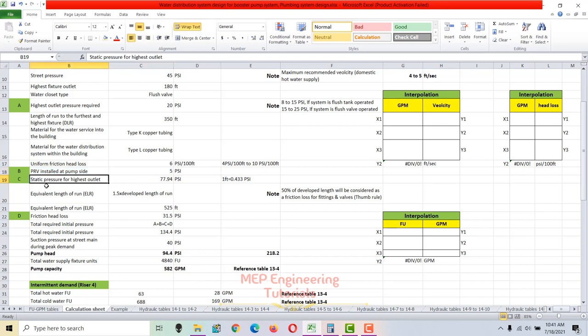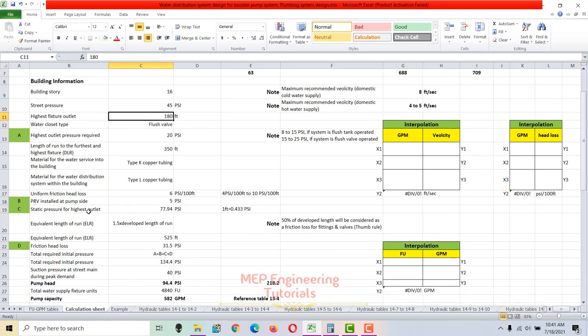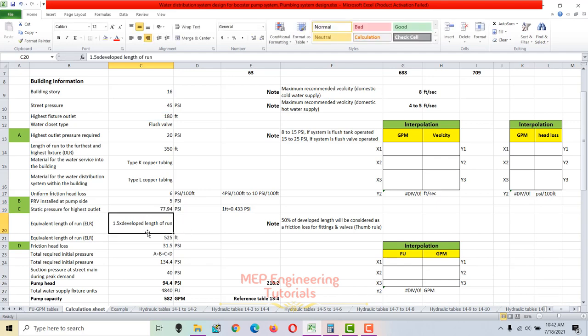Next, we calculate the static pressure for the highest outlet. The highest outlet is 180 feet above the pump level. Using the conversion of 1 foot = 0.433 psi, the static pressure for the highest outlet is 180 × 0.433 = 77.94 psi.